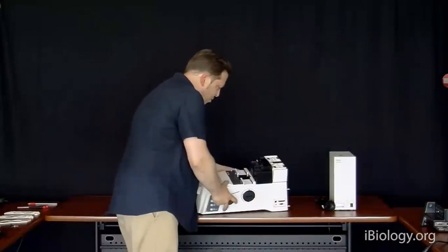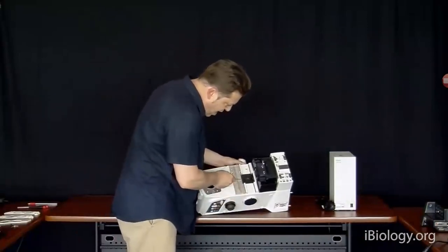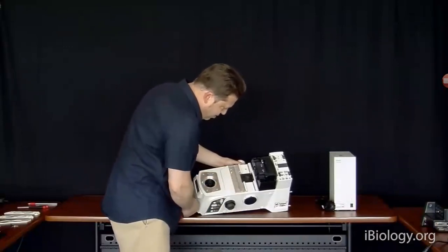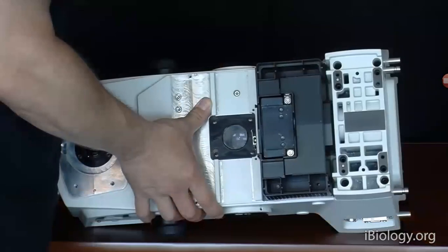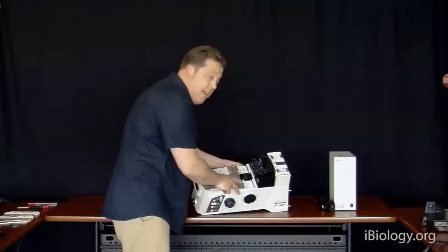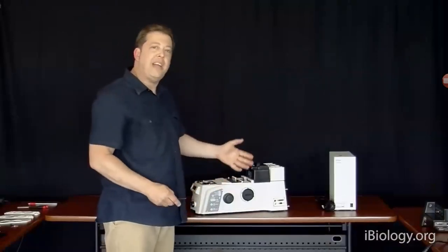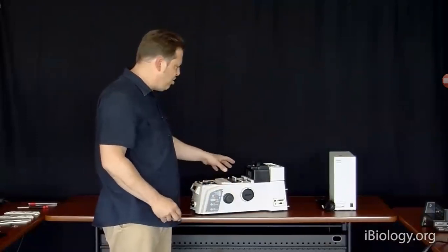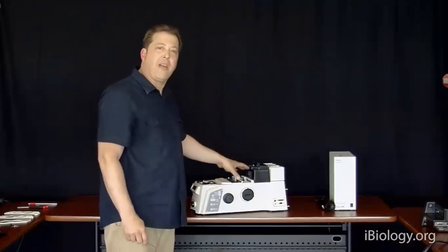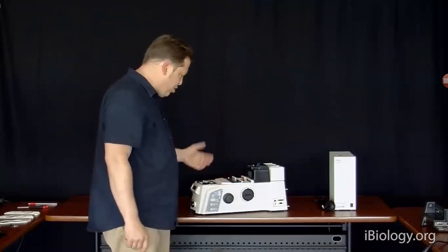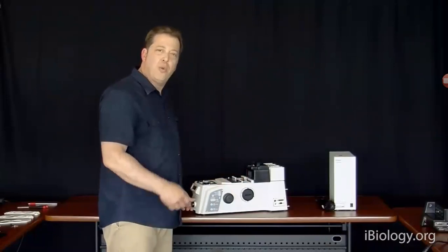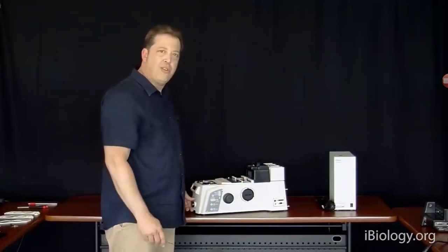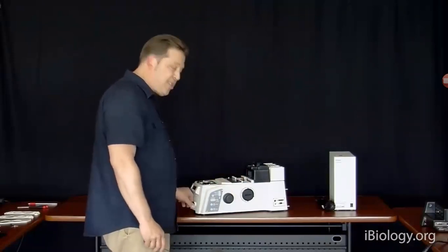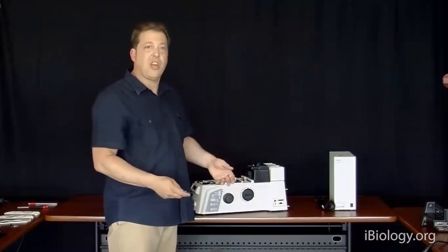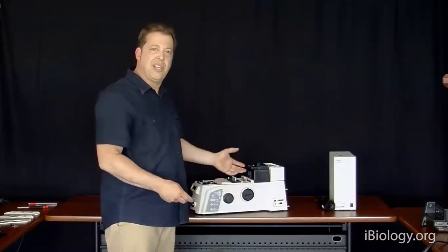And here we have what's called the tube lens of the microscope. And one thing I want to show you, you can see this microscope actually has two different tube lenses in it. I don't know if you can see that very clearly, but we're changing the tube lens in the microscope. In an infinity optical system, the magnification that the microscope achieves is a function of the focal length of that tube lens. So what we do is we have two tube lenses, one at 200 millimeters, which is 1x magnification, one at 300 millimeters, which is 1.5x magnification. And by switching those tube lenses, we can achieve higher magnifications without having to add more glass to the system.